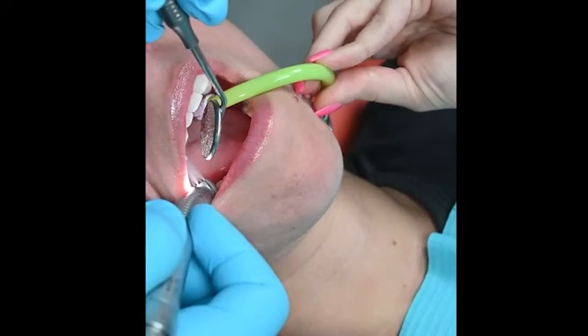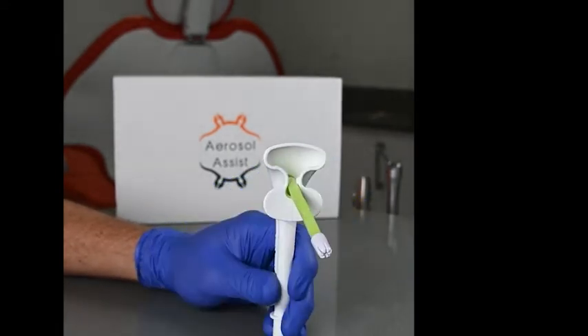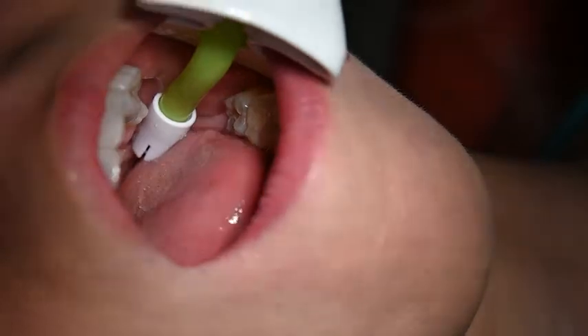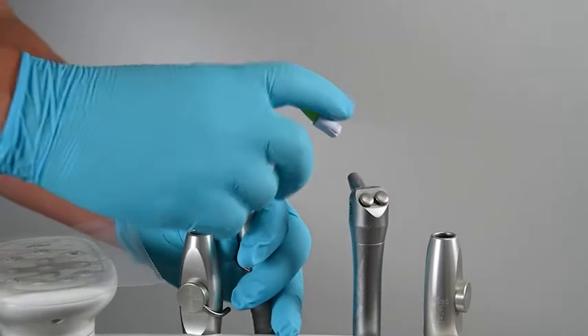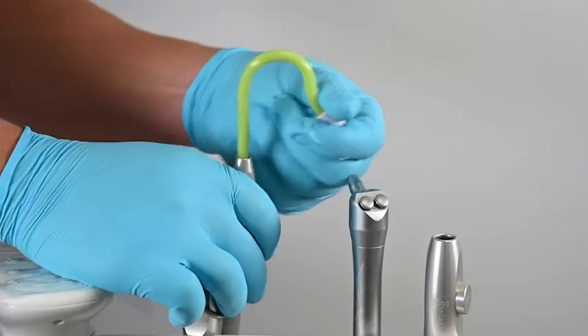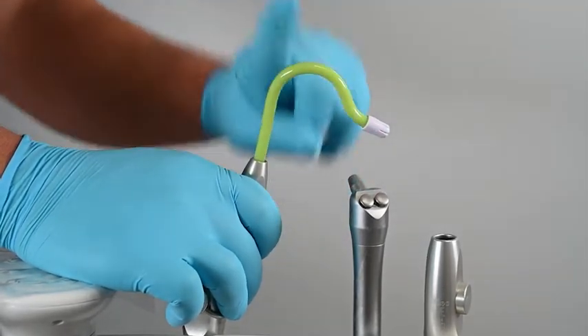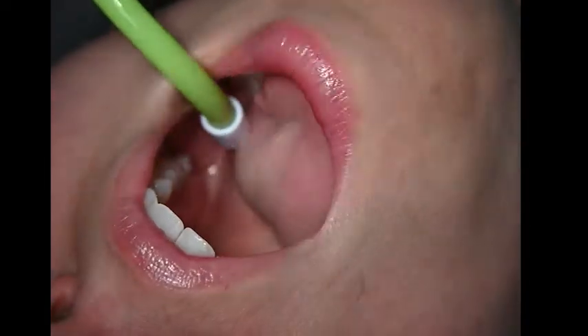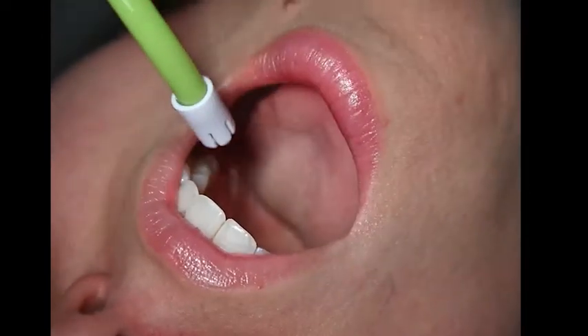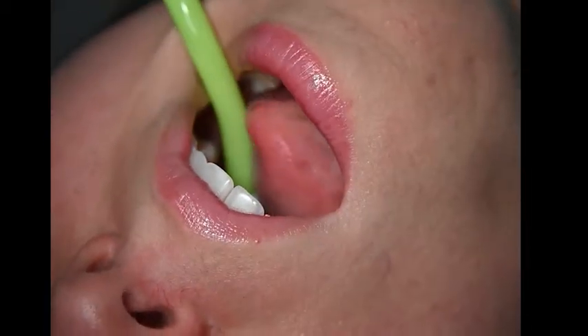The saliva ejector — from falling off, being picked up by patients due to it being uncomfortable, or just doing its own thing after you find the optimal position — is long overdue for an upgrade. The aerosol assist is designed to upgrade the functionality of a standard disposable saliva ejector so that it can be truly customizable, comfortable, and easy to use. When working with only a saliva ejector, a proper position can be achieved by creating two bends on the body. The first bend is to anchor the saliva ejector to the lip, and the second bend is to angulate the tip to remove intraoral fluids. Because of the variability in patient's anatomy, where to place the bend is arbitrary and is achieved through trial and error. This causes another problem: when you put the saliva ejector into a patient's mouth 100 times, you'll get 100 different positions because of the arbitrary nature of bending the saliva ejector. We resolve that issue by using the anatomy of the aerosol assist to aid in getting consistent results.